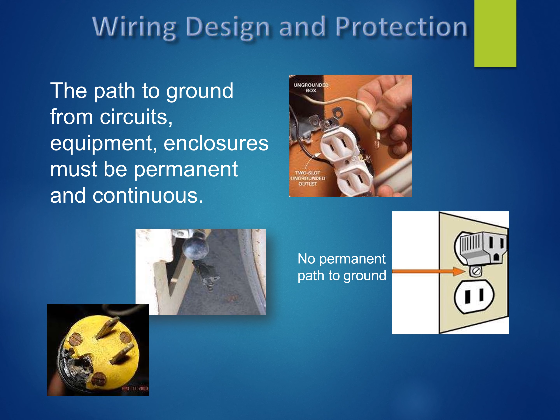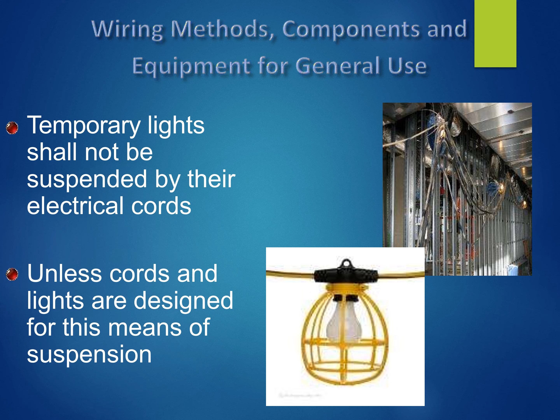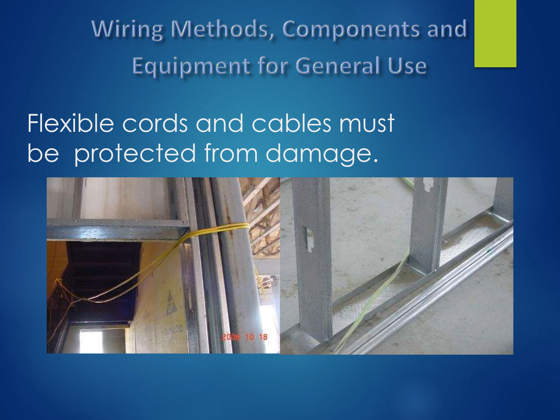Just to show you, temporary lights shall not be suspended from anywhere, for safety, because if the cord for your temporary wiring is cut or there is a sign of abrasion, that is unsafe. Here, flexible cords and cables must be protected from damage. Meaning, if you are installing a flexible cord or cables in the walls, you have to protect your cable. Otherwise, it will touch the metal, and that will cause electrocution of other personnel.